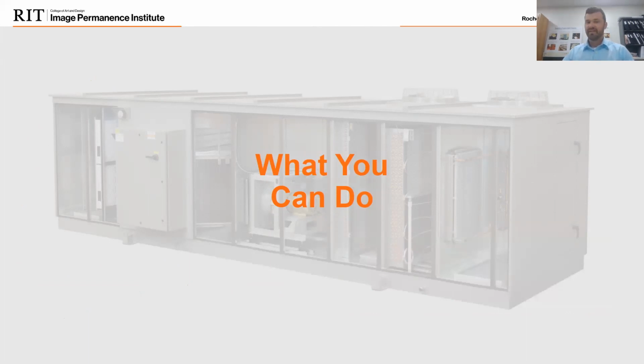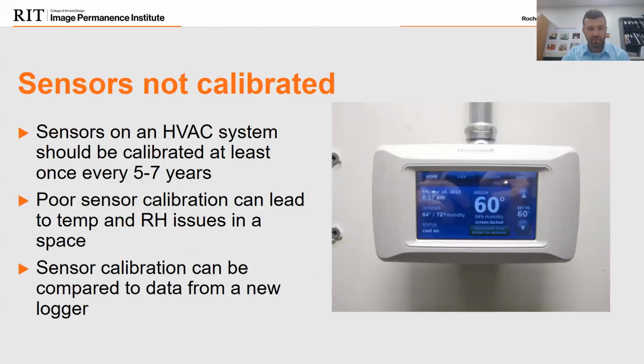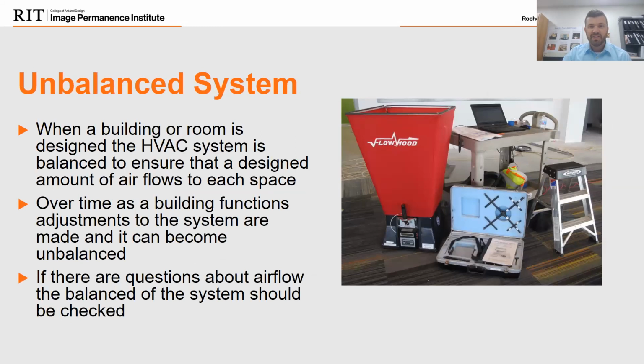And while it's in mind, can you describe what's involved with balancing? So when we talk about balancing, you'll see that little red hood, and whoever your balancing specialist is may use different systems. They'll put that red hood literally right over a diffuser and check the CFM of the air coming out. They'll compare it to the original prints of the unit and the space, and say this diffuser was designed to put out 400 CFM, and it's now putting out 220. So they'll know they have to make an adjustment.